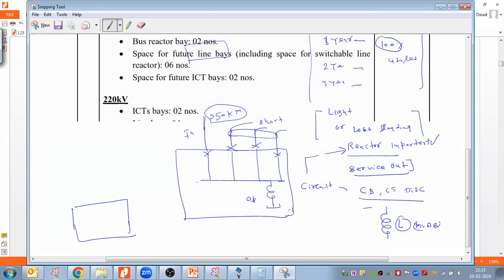In that case, I can connect this reactor in parallel with this line bay instead of connecting it on the bus bar. And since this reactor is connected in parallel with the line bay, I cannot connect it in series - note this down, because if I connect it in series, how will I isolate it in the future? So I have to connect this reactor in parallel.